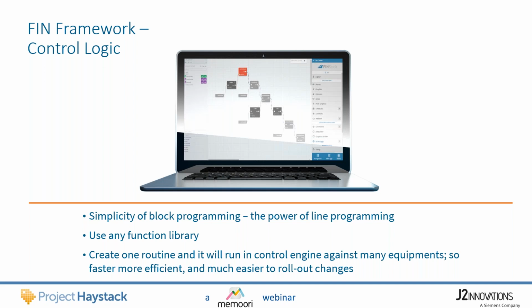Instead of having threshold alarms in all the different devices around the system, with Fin Framework you can query the data dynamically and create a more intelligent, smart strategy for a better quality of alarm. Instead of just checking if it's over a threshold temperature, you can say: is it over temperature for half an hour, and have I checked that the air handling unit and fan coil haven't been turned off for maintenance? This really is an alarm.